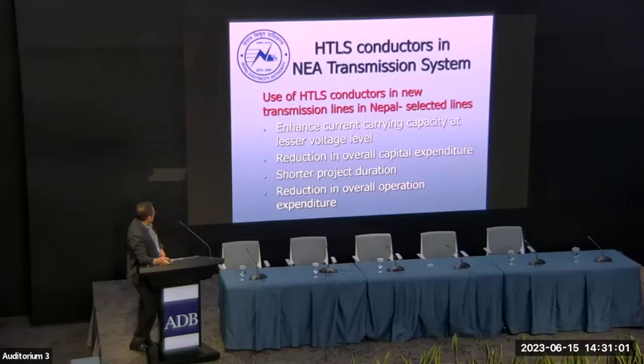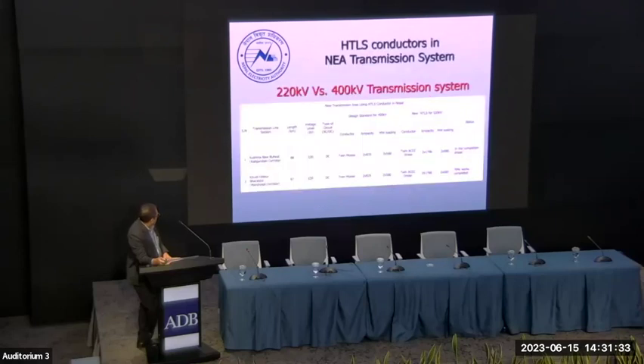Why did we do this? It can carry higher transmission power even at a lesser voltage, and requires a smaller right-of-way, so the project duration is shorter. We face fewer challenges than with a 400 kV transmission line, because a 400 kV line takes nearly 45 meter right-of-way, but with 220 kV we use only a 30 meter right-of-way. These are the two corridors we used.